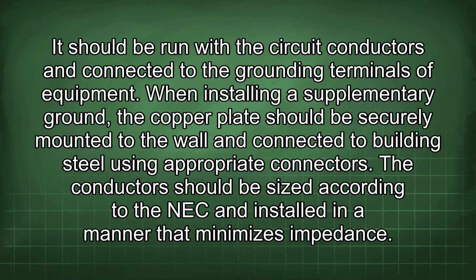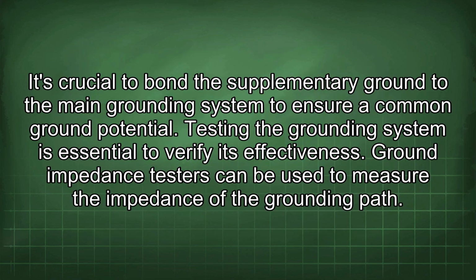When installing a supplementary ground, the copper plate should be securely mounted to the wall and connected to building steel using appropriate connectors. The conductors should be sized according to the NEC and installed in a manner that minimizes impedance. It's crucial to bond the supplementary ground to the main grounding system to ensure common ground potential. Testing the grounding system is essential to verify its effectiveness.